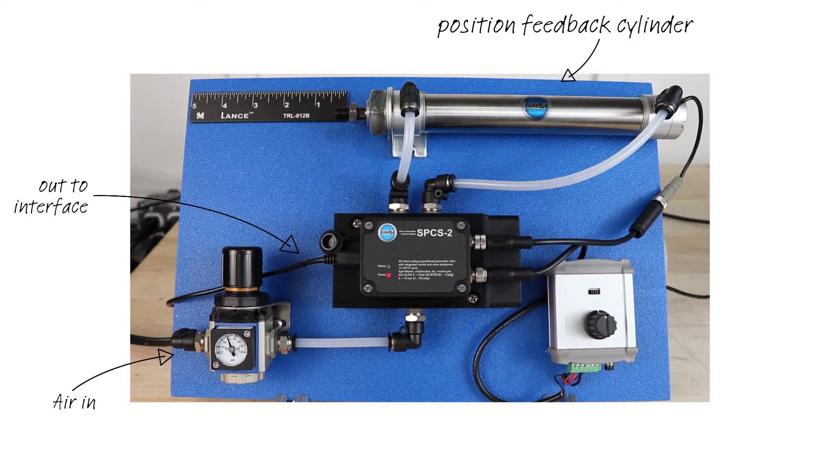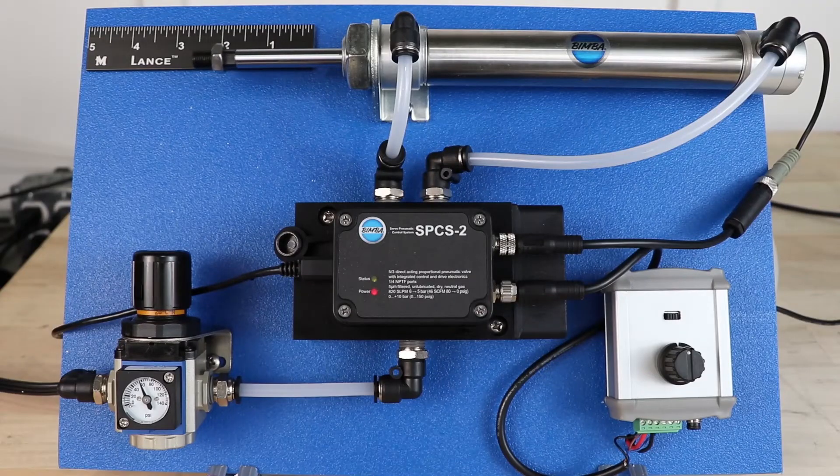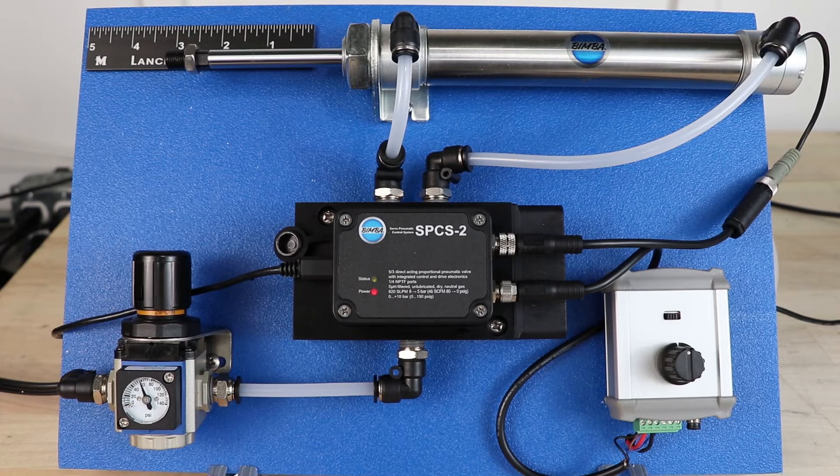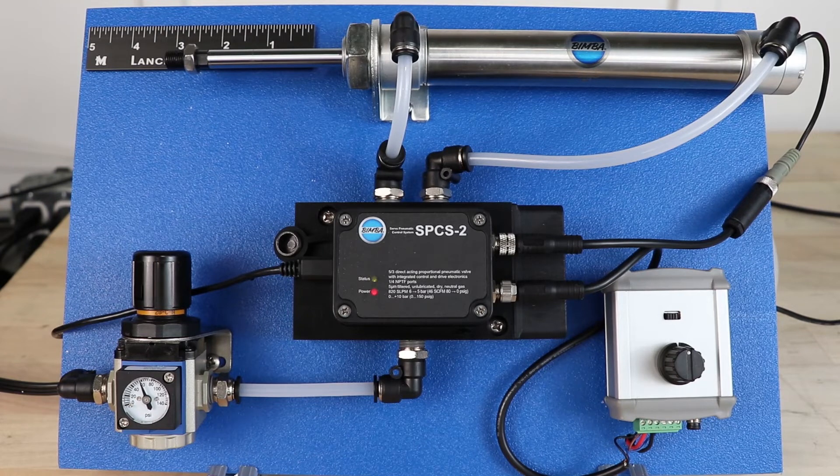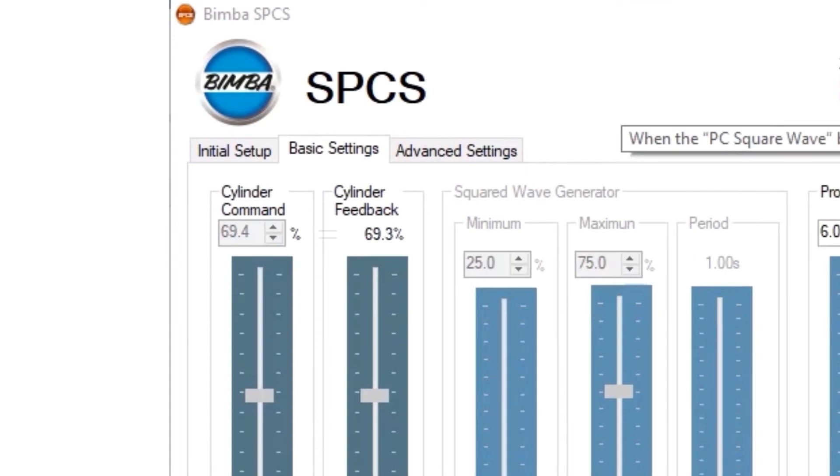On a technical level, when in operation the SPCS2 valve receives a command signal and supplies enough air to extend the rod. The actuator sensor then sends feedback on the rod positioning, causing the valve to generate additional power until the feedback voltage equals the command voltage.